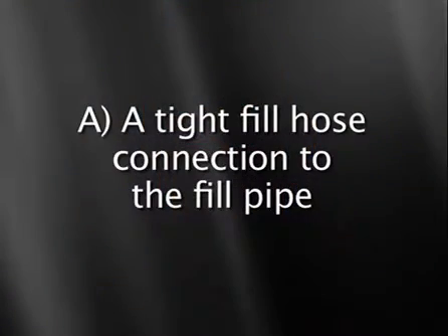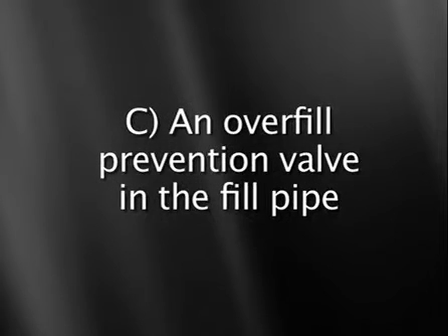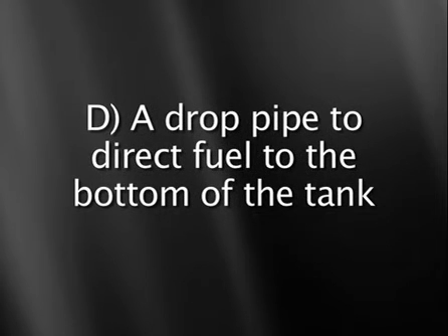The basic components of the fill system are: A, a tight fill hose connection to the fill pipe; B, a spill container surrounding the hose connection point; C, an overfill prevention valve in the fill pipe that automatically closes on high level; and D, a drop pipe to direct fuel to the bottom of the tank and minimize turbulence.